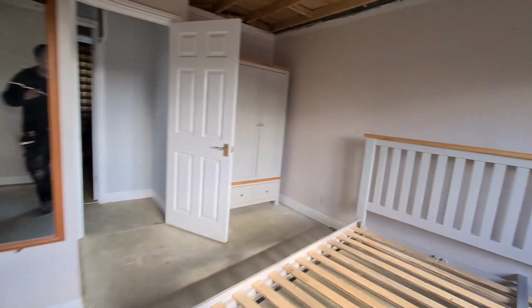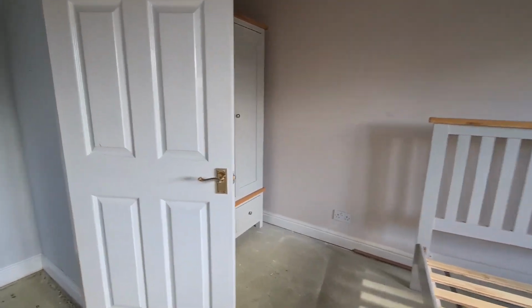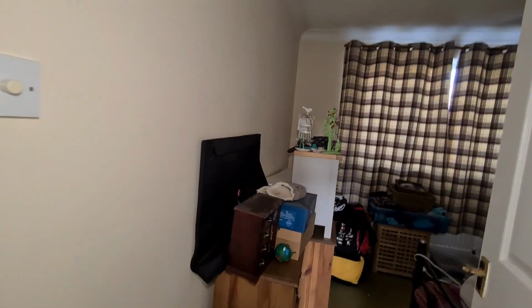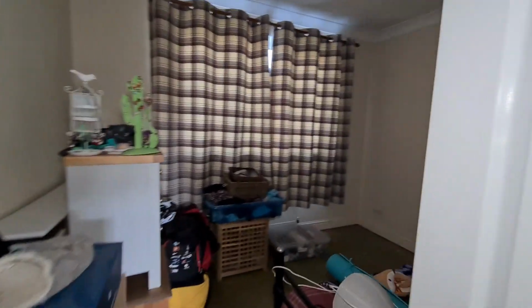We've had a lot of water ingress to electrical accessories. It's flooded all the way through these walls. These were all soaked - it's got into all of the sockets as well. The light bulbs themselves were full of water, so it's obviously been leaking into all of those, and they're actually sizzling away. The lights hadn't tripped, they just weren't working because there's lots of sizzling and arcing going on.